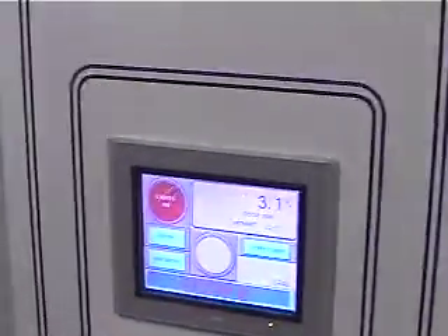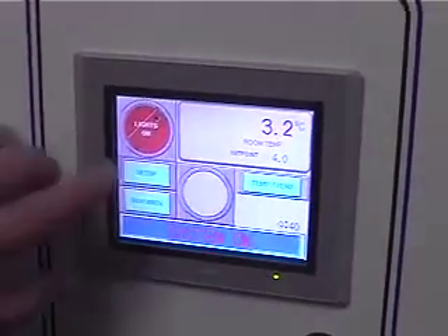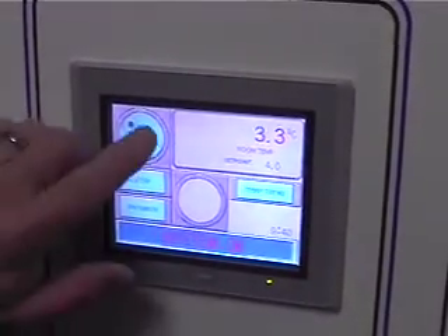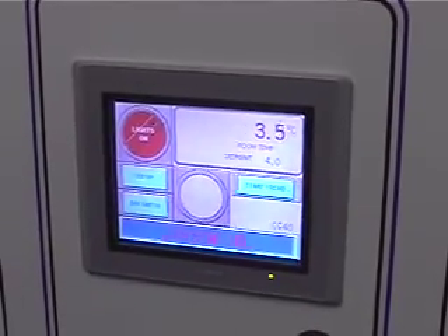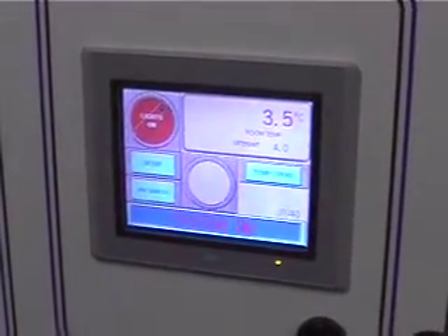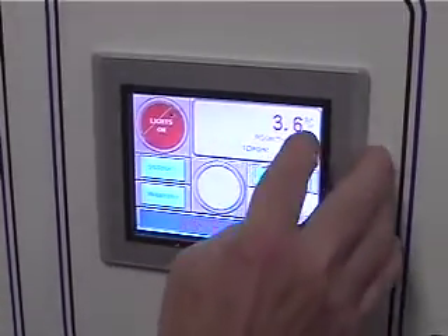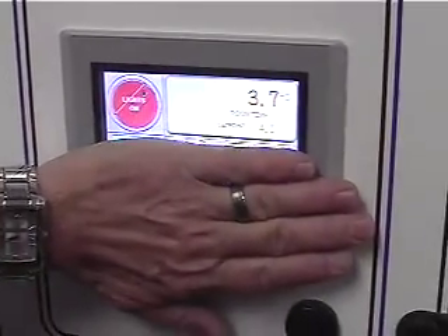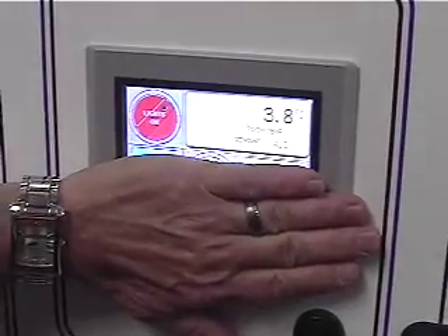So we have a delay period that we've built into these things. It's adjustable. If you have a nuisance alarm, and it's usually a high temperature, you just increase the delay period. It beats actually spreading out the high temperature, because if you actually have a high temperature issue, now you just make the problem even worse. Lights, no more switches. We do it virtually right on the control console. By doing that, we can also give you the opportunity to turn it off if they're not getting turned off. Real-time temperature and real-time set point. If you change the set point, it'll register right there as well.